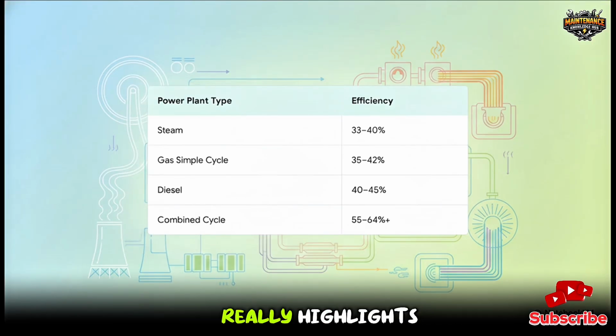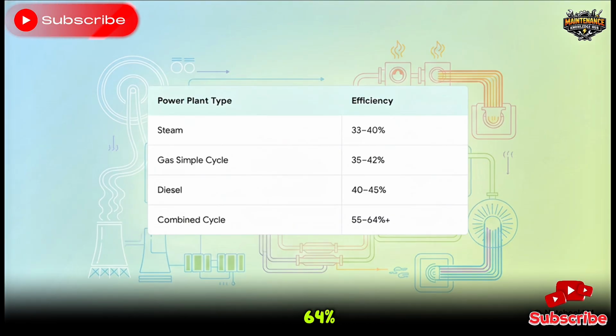Comparing these numbers really highlights the impact of this dual-cycle technology. I mean, a traditional steam power plant hovers around 33 to 40% efficiency. A simple cycle gas turbine is slightly better, hitting maybe 35 to 42%. A diesel plant might hit 40 to 45%, but look at the combined cycle power plant at the bottom. We leap all the way up to 55 to 64%, with some advanced plants pushing even higher. By recovering that waste heat, the efficiency advantage is truly massive.